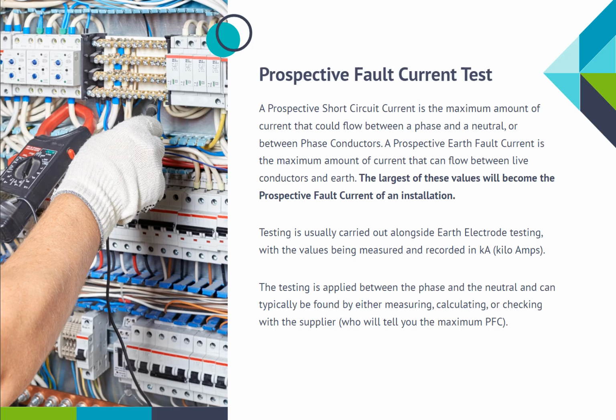Testing is usually carried out alongside earth electrode testing, with the values being measured and recorded in kA, kiloamps. The testing is applied between the phase and the neutral, and can typically be found by either measuring, calculating, or checking with the supplier, who will tell you the maximum PFC.